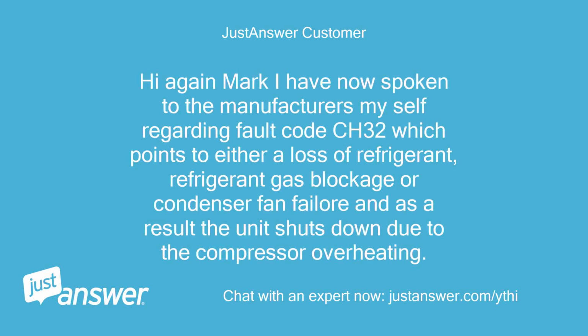Hi again, Mark. I have now spoken to the manufacturers myself regarding fault code CH32, which points to either a loss of refrigerant, refrigerant gas blockage or condenser fan failure, and as a result the unit shuts down due to the compressor overheating.